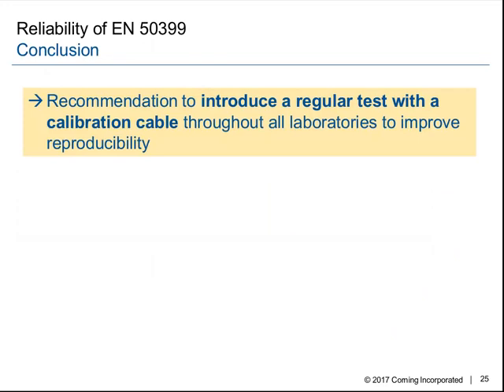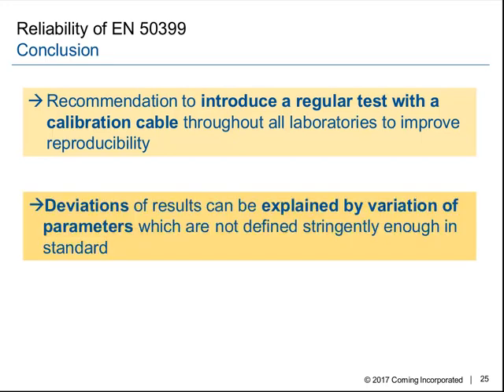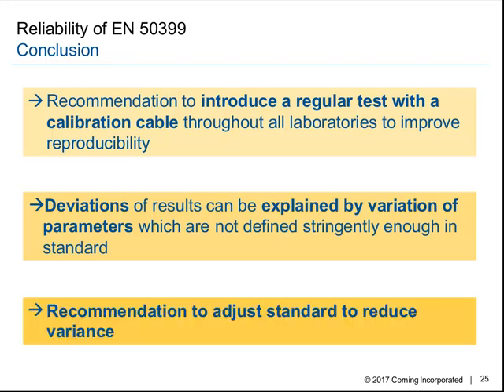So my conclusions in the end. I showed you the calibration cable, and we recommend introducing a regular test with such a calibration cable throughout all laboratories in order to improve and monitor the reproducibility. I showed you that the deviations which were observed, we could explain by the variation of parameters which are not defined stringently enough in the standard. And we recommend adjusting the standard in order to reduce those variances.